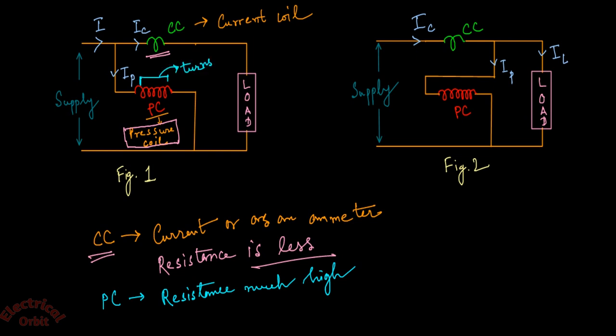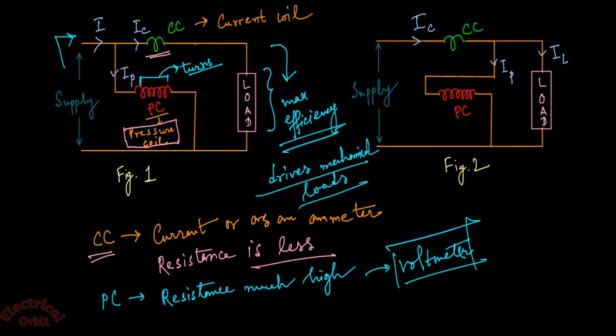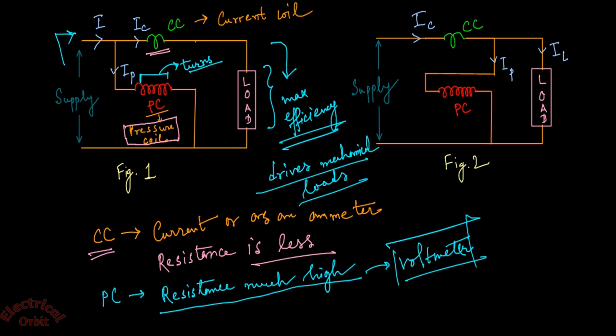Conversely, in the pressure coil the resistance is much higher, so it has a higher number of turns — similar to a voltmeter whose internal resistance is very high. This ensures very little current passes through it, because whenever we connect a load to the system we want the major part of the supply current to pass through the load for maximum efficiency. So the voltmeter or pressure coil resistance is always kept high.